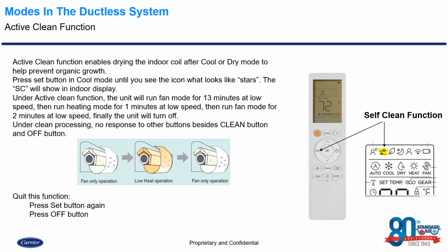Essentially, what we're doing with the self-clean function is preventing organic growth, mildew, or any funky smells from building up on that interior coil because of the moisture that naturally occurs during cooling operation. This does not take the place of cleaning coils and routine maintenance, but depending on your customer, it may be something that you want to recommend to them based on their lifestyle. Okay, it's also important to understand that customers may think that this means it cleans the filter by itself, and that is not the case. They still need to do their due diligence, take the filters out, lightly dust them and clear away anything that's impacting them, and then put them back in.